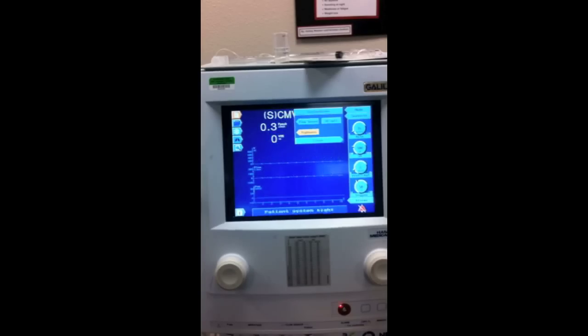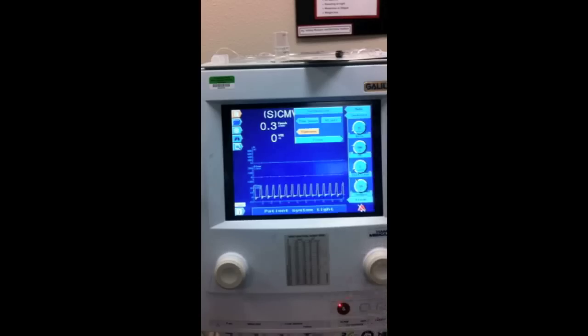It's actually running the test now. It says patient system tight. Now it's trying to deliver a breath. So if you get to this point where it's just automatically cycling, what it thinks is happening is my ET tube is occluded because my hand's over it. So that's why it's just dumping.